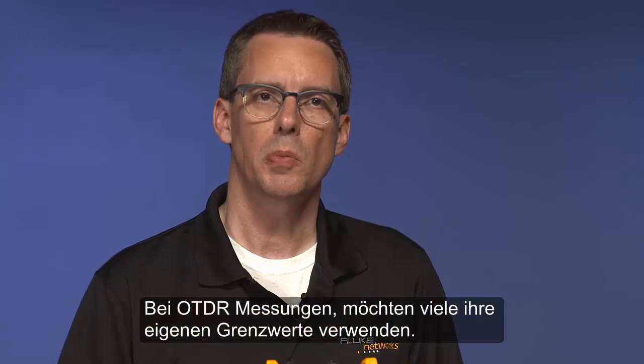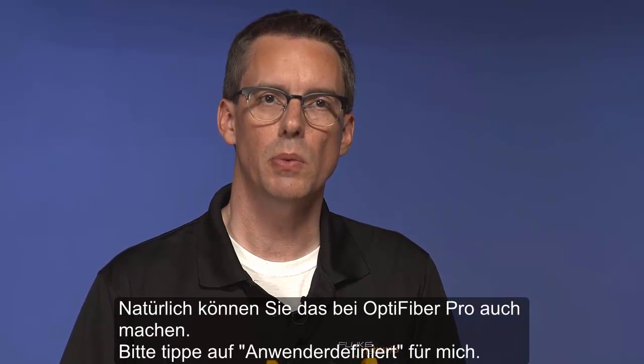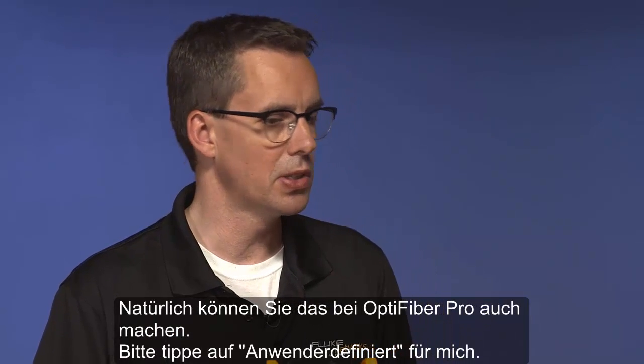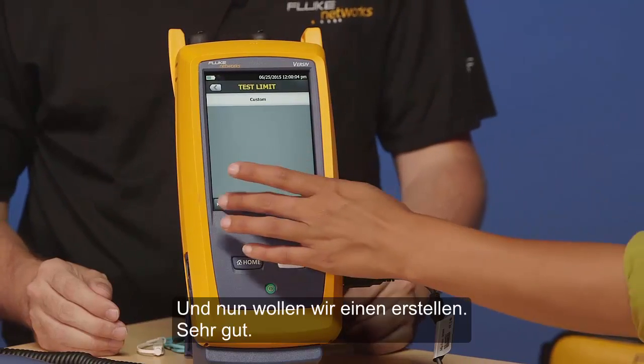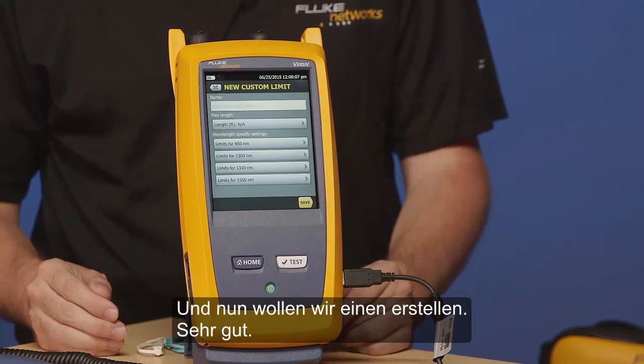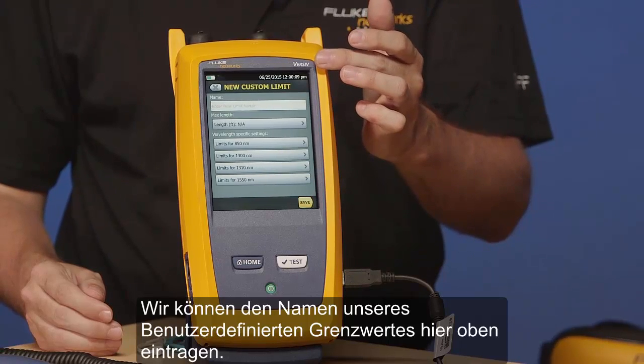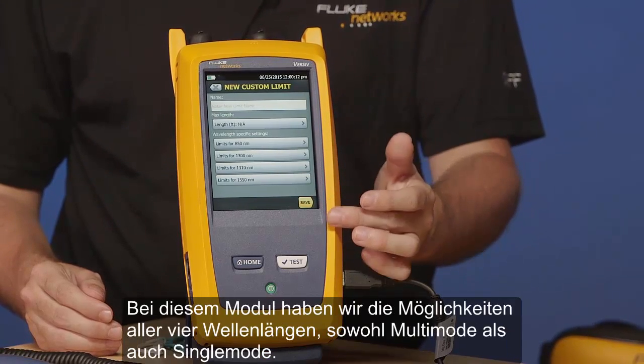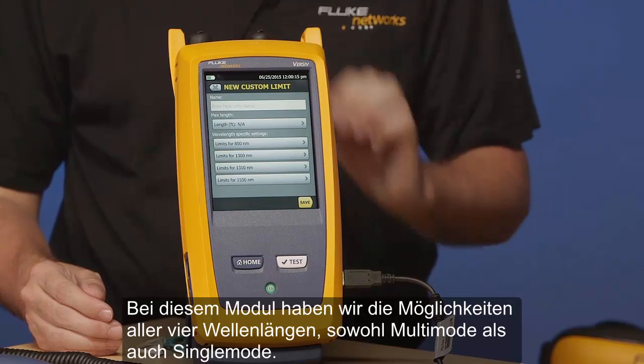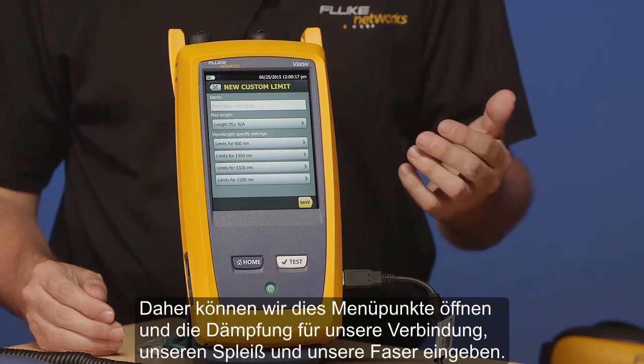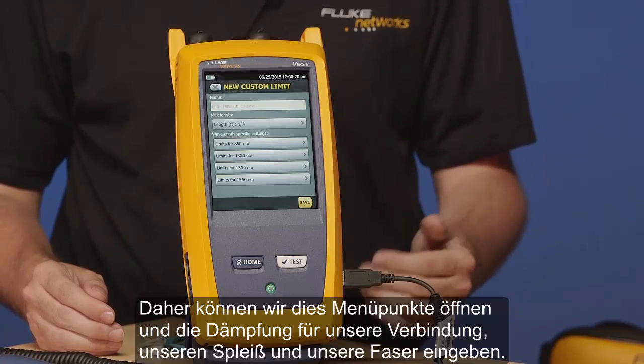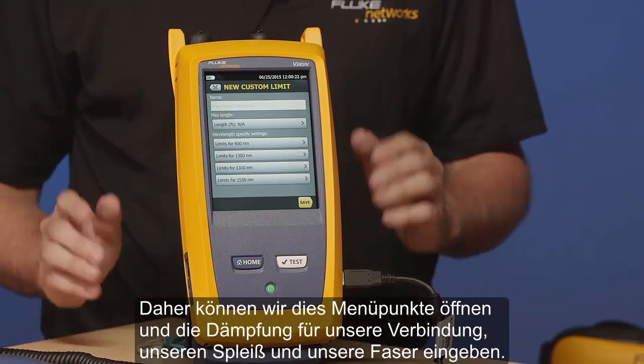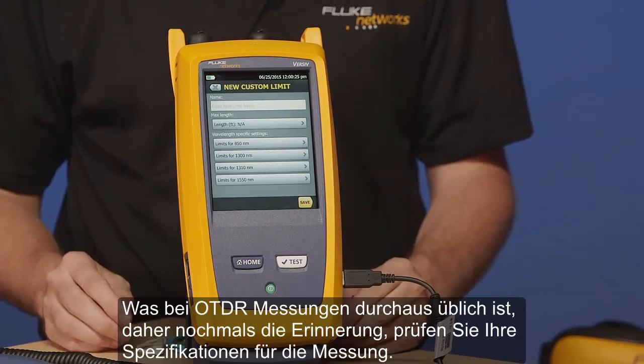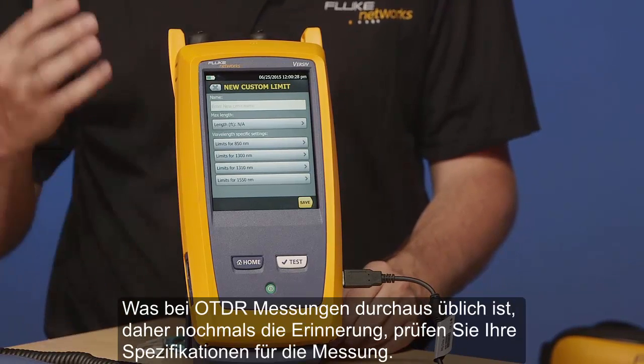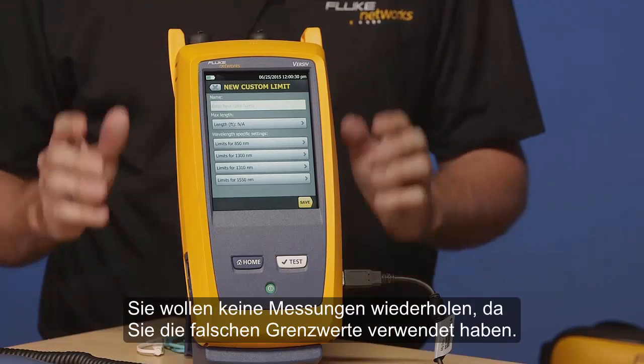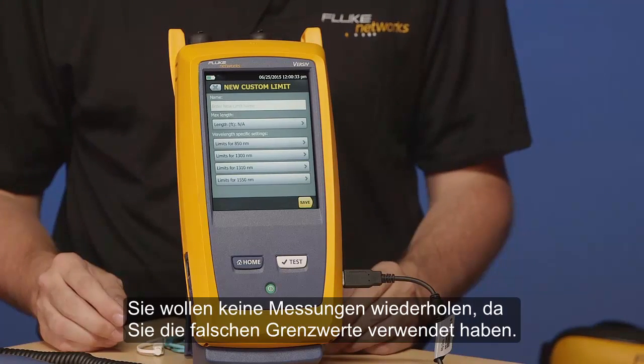With OTDRs, a lot of people like to use their own test limits, and you can do that with the OptiFiber Pro. Go ahead and tap on Custom for me. And yep, we're going to go and create one. Excellent. So we can put the name of our custom test limit in the top here, and we have the four wavelengths that are supported with this module here, both multi-mode and single mode. So we can go into those menus and add in our connection loss, our splice loss, our fiber loss, and test to a tighter specification. And that's very common with OTDRs, which again is another reminder, please check your test specification. You don't want to be retesting because you selected the wrong test limit.